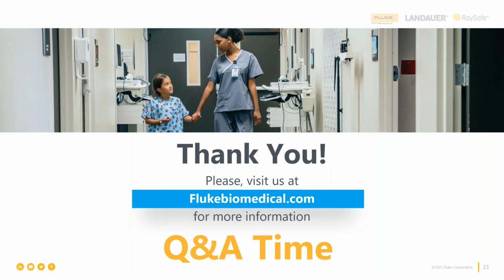Next question is, how do you measure protective earth? Well, it's an ohmic, it's a resistance measurement. We're not doing an electrician's test where you're testing that the ground is appropriately conductive all the way to where a conductive rod is driven into the earth. That's not the testing we're doing. We're not doing what they call in Europe installation testing. That's not the biomed's job. That's the electrician's job. What we're testing is the resistance of the protective earth pathways, which should be the lowest possible resistance value of any conductive pathway on the medical device.